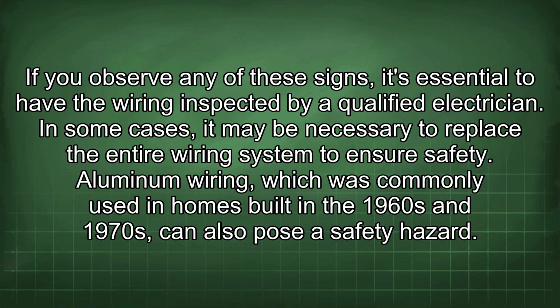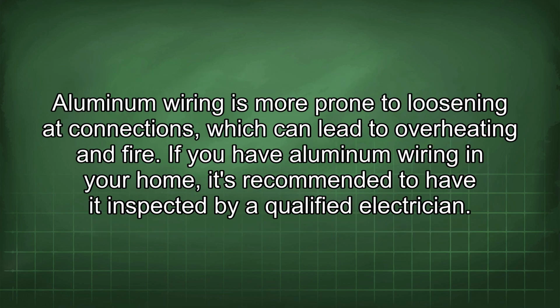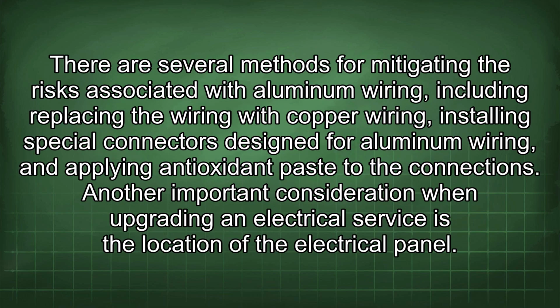Aluminum wiring, which was commonly used in homes built in the 1960s and 1970s, can also pose a safety hazard. Aluminum wiring is more prone to loosening at connections, which can lead to overheating and fire. If you have aluminum wiring in your home, it's recommended to have it inspected by a qualified electrician. There are several methods for mitigating the risks associated with aluminum wiring, including replacing the wiring with copper wiring, installing special connectors designed for aluminum wiring, and applying antioxidant paste to the connections.